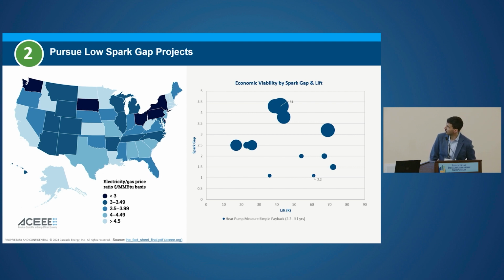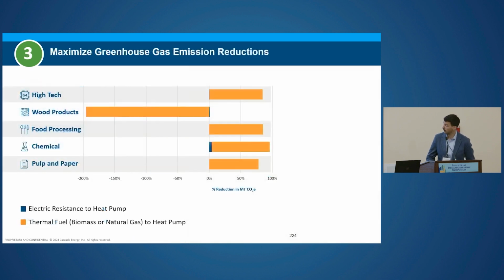But it's interesting to note that for spark gaps below 2, those projects delivered the quickest paybacks, the smallest bubbles there. And that was even for a range of lifts. So we know that lift is a key factor that drives COP. But in this case, as long as the spark gap was low enough, the project looked pretty good. So I think that's a key takeaway. Some of those larger bubbles were those food processing sites, which had a higher spark gap. So that's why those projects didn't pan out.